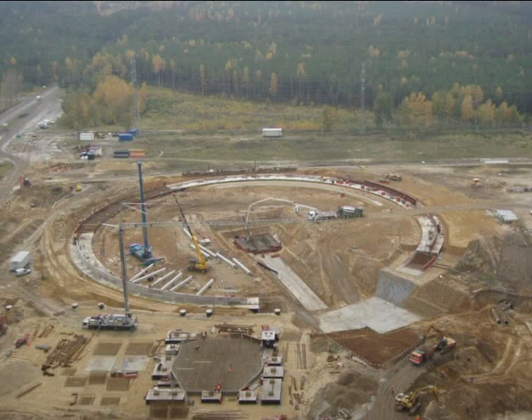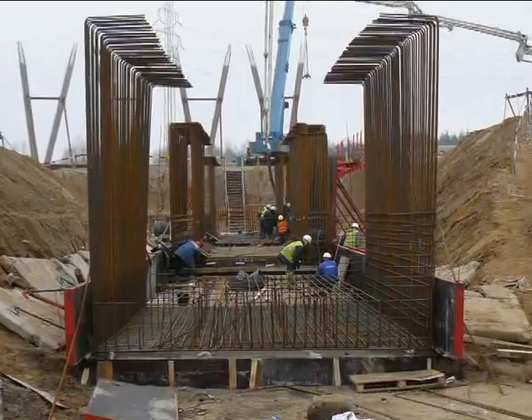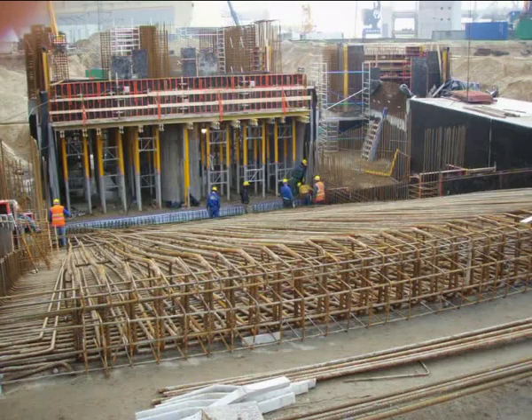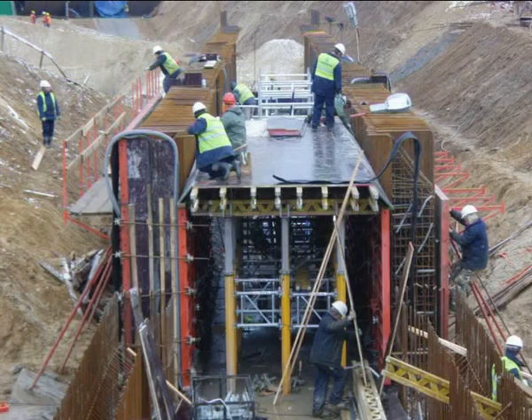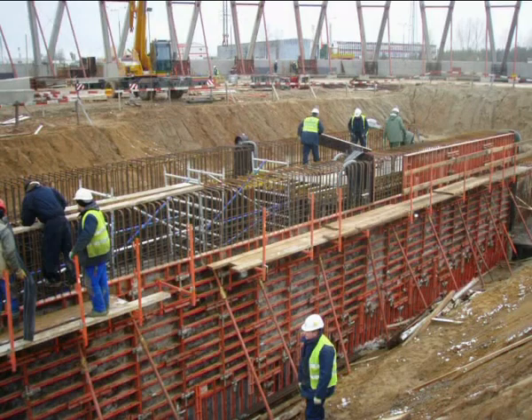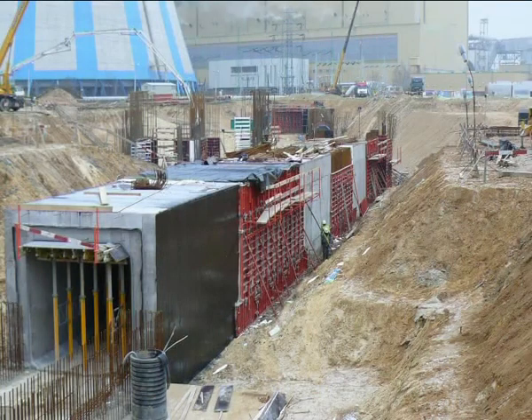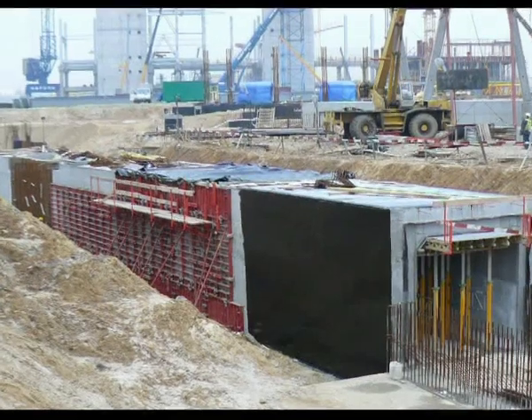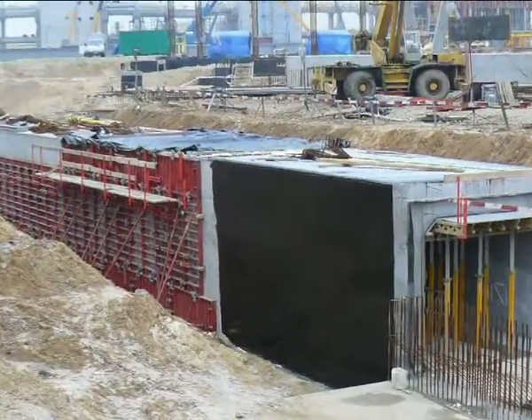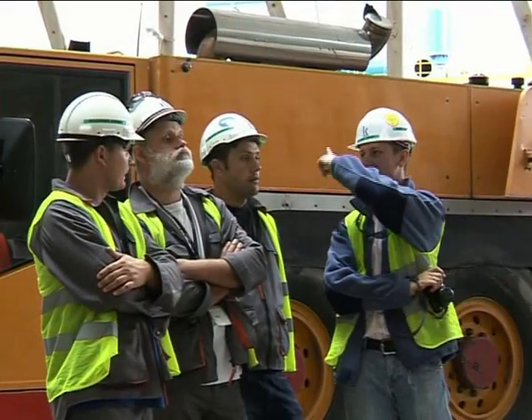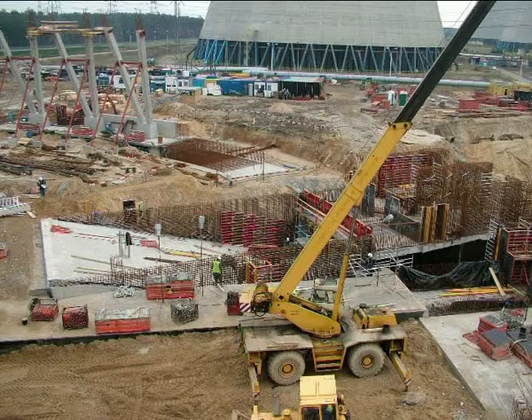Construction of the underground conduits to carry the hot and cooled water was started in September 2007. A hot water pipe was constructed inside the tower, measuring 4.9 by 4.9 metres and 50 metres long. 220 tonnes of reinforcing steel and 1,500 cubic metres of waterproof concrete were used for its construction. Cooled water is returned via a reinforced concrete chute with a drop of 15 degrees.